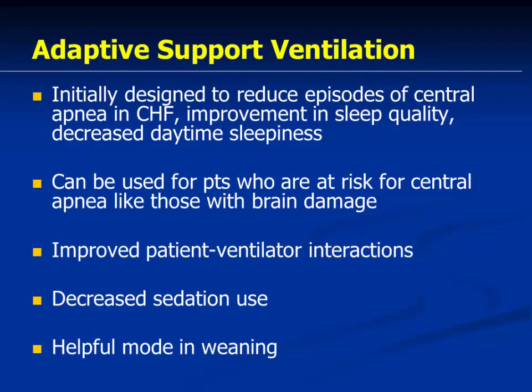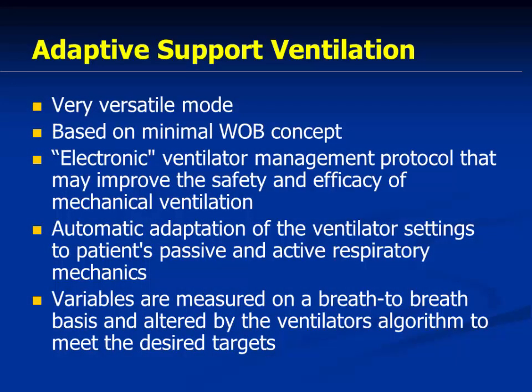Same thing, I have missed one slide. Same thing can happen in the expiratory phase also. Try to understand, when patient is trying to expire, again the resistance is there. You have set a PEEP of 5, but actually because of that resistance, that PEEP might be little higher. So in the expiratory phase, what does this mode do? They calculate again the resistance and bring the PEEP level down a little bit. So at the initiation of the expiration, the pressure comes down below the PEEP just to facilitate the expiration, and then it maintains at the level of the PEEP.